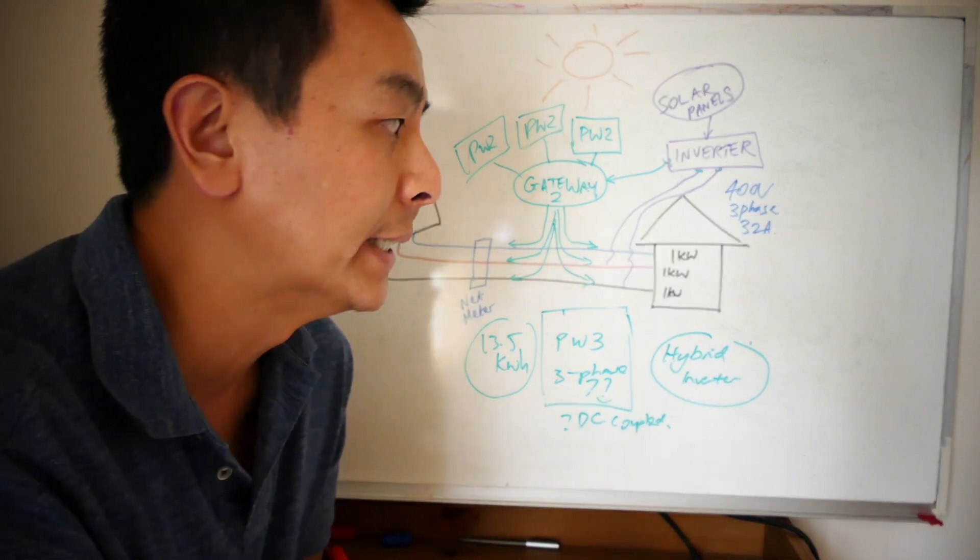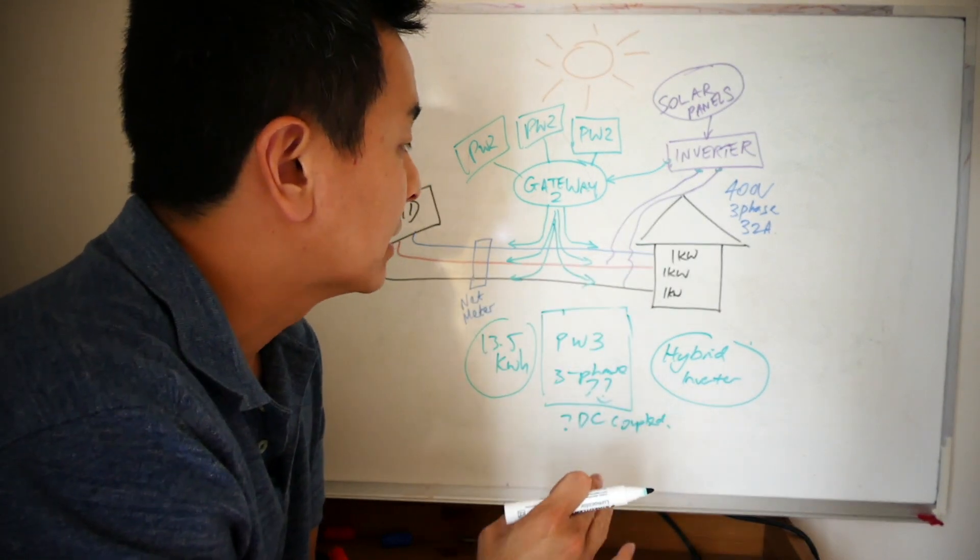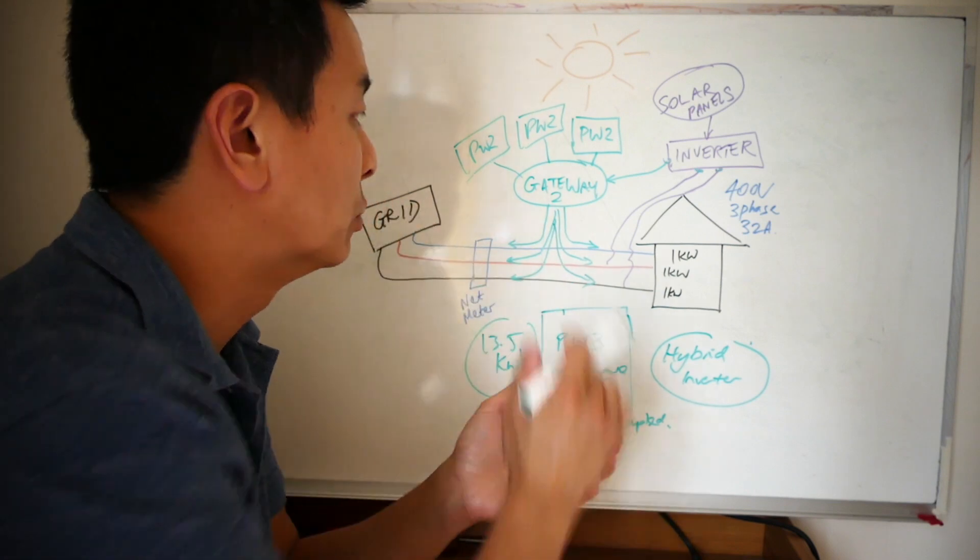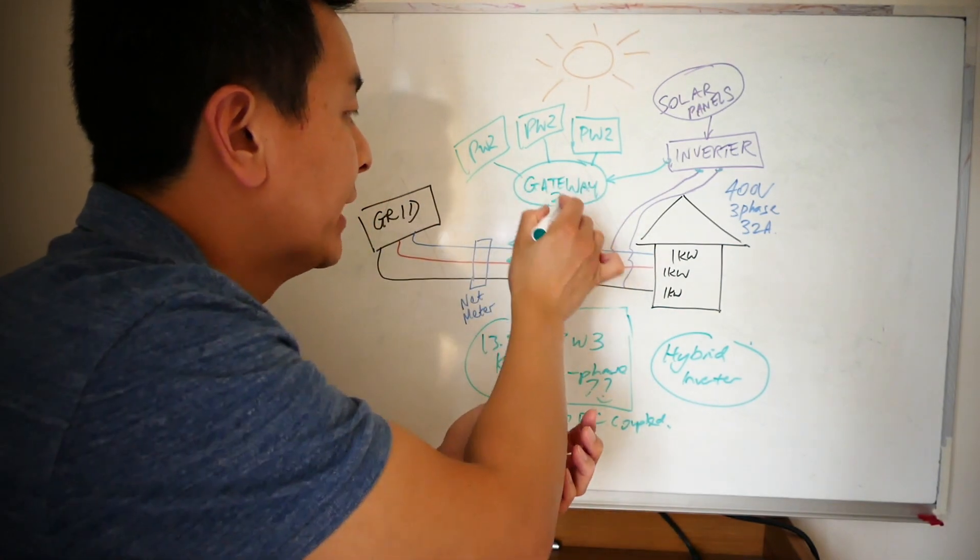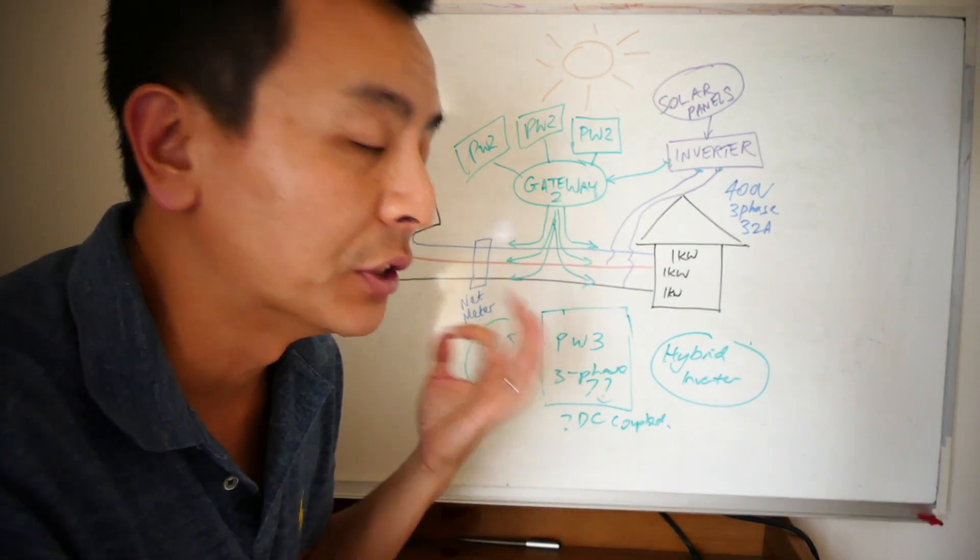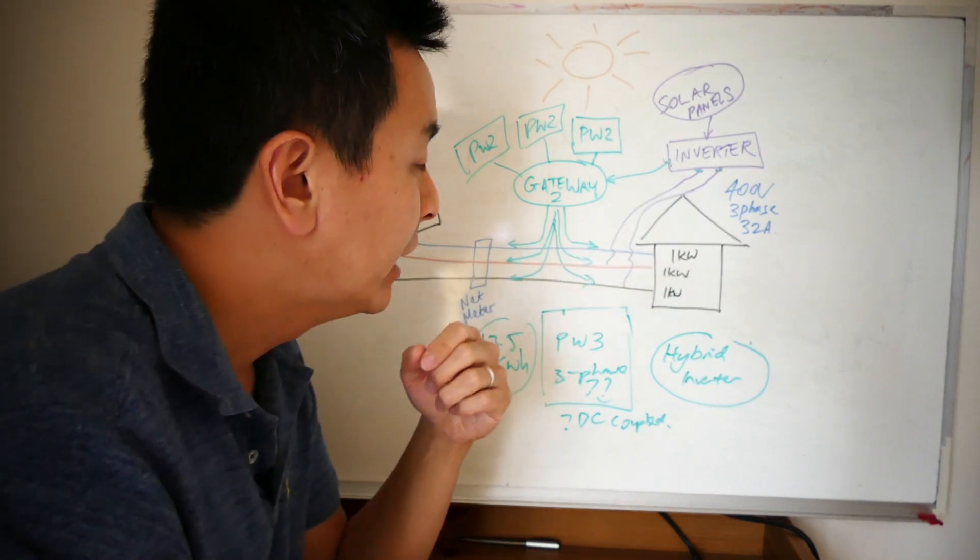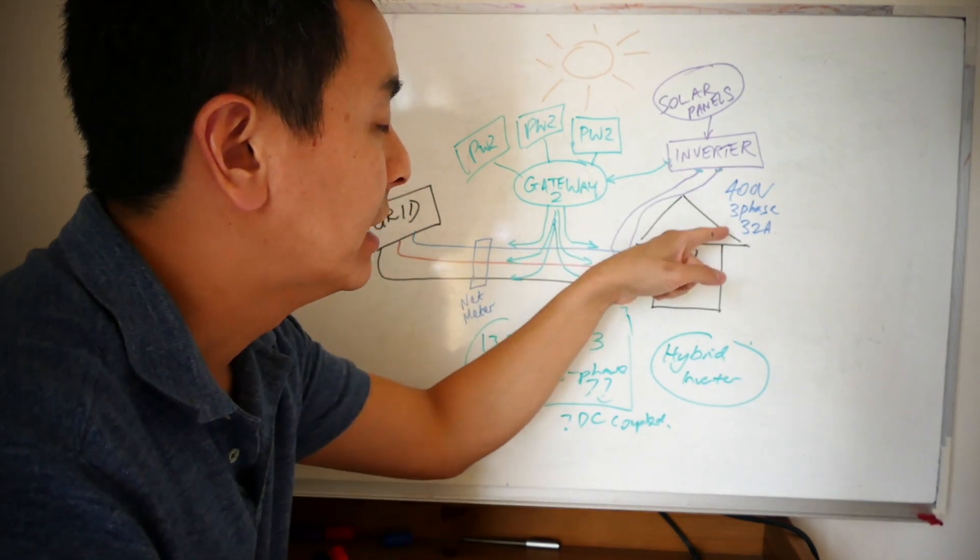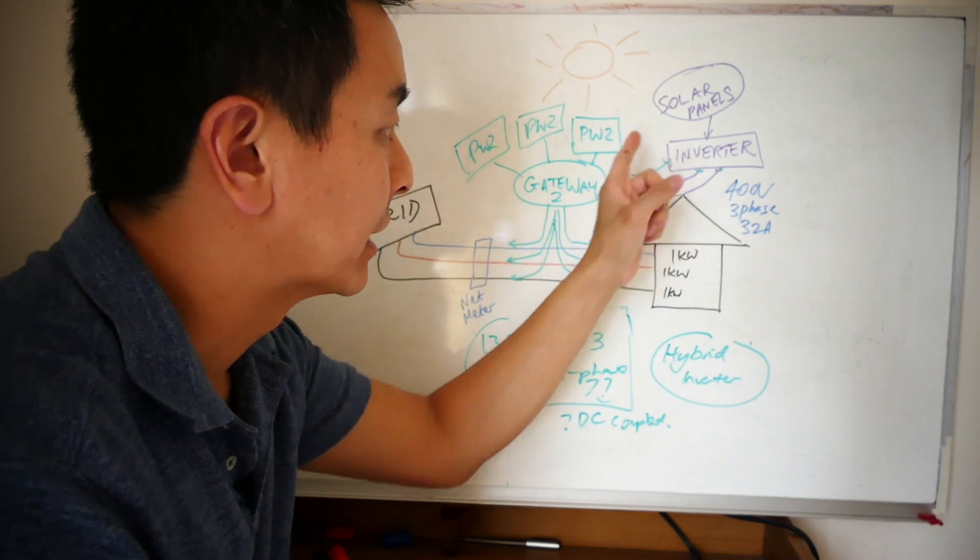Anyway, so I hope that makes sense. It's impossible for Powerwalls on each phase, even if you're using a Gateway 2 which is three-phase compatible, to power a 400 volt three-phase supply device like a solar inverter.